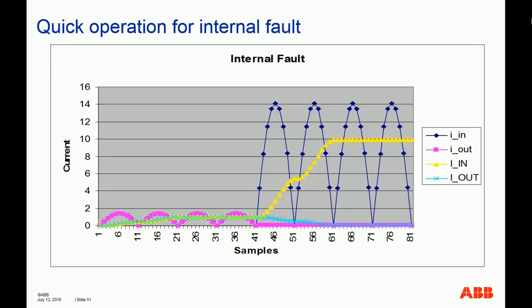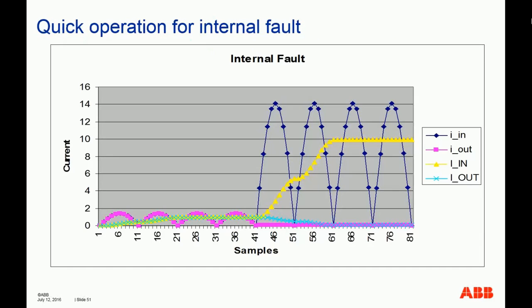Here is some graphical explanation of how modern relays operate for internal or external faults. In this case, as you can see, we have instantaneous values signified by the green, the blue and the pink. These are your sinusoidal waveforms, if you like. You can see a standard load current flowing here. All of a sudden, the fault hits.